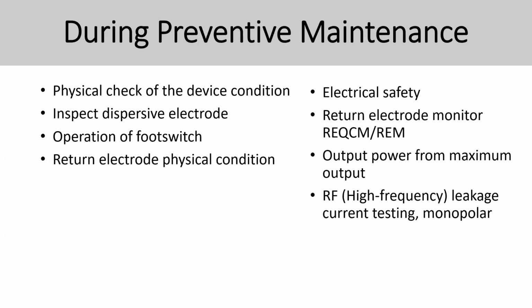When you talk about performance and electrical safety, you're going to do electrical safety first of all. So with electrical safety, basically you're going to look into user safety, patient safety, and the equipment, whether it has any leakage or not. Then you have return electrode monitoring. Basically, you're going to perform the return electrode performance check. You want to check whether it's really working well with the device or not. Then output power from maximum output. Then radio frequency leakage. So all these are very important. When you talk about radio frequency, high frequency, you're going to do leakage current testing, especially on the monopolar, because if your leakage current is too high, you're going to affect the patient actually.